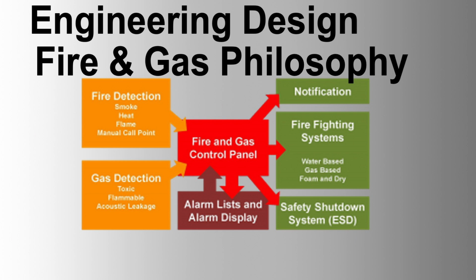Initiating audible and visual alarms via PAGA systems. Activating shutdown actions via IPS. Providing system status indication and alarms at ICSS operator consoles. Ensuring extensive self-testing, fault monitoring, and diagnostics facilities for continuous and periodic testing purposes. Gas detectors must be smart HART type with 4-20 milliamps output. The fire and gas systems should communicate over a redundant network with a common PC and printer provided at the control room for SOE and programming functions.